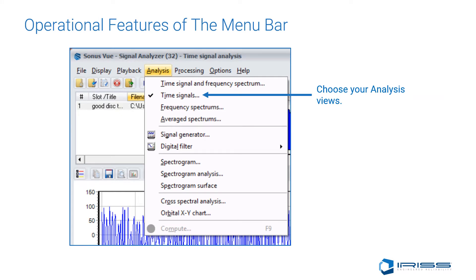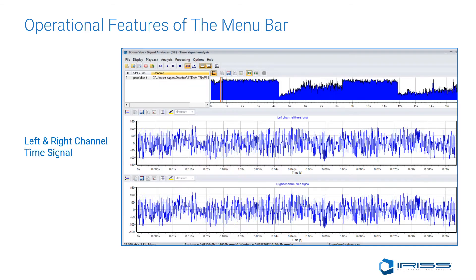When analyzing the sound wave, the analyst has several options to choose from. The default view in Sonus Vue Pro is the dual time signal, which displays both left and right channels in a time signal format. The dual left and right time signal screens allow the CBM analyst to view the sound wave in linear phase — a straight-line view of the sound energy. Ultrasound devices that record mono signal will show up as non-linear phase, and only the right time signal will show since they have no left channel.